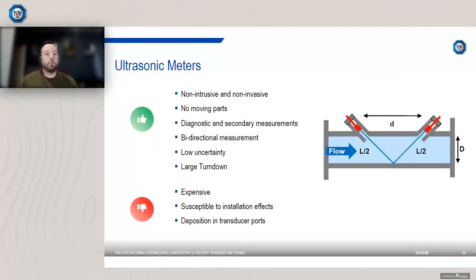So why are ultrasonic meters popular for custody transfer applications? Well, they're non-intrusive and non-invasive, so they're not typically going to introduce a pressure drop in the pipeline, and you can even get clamp-on ultrasonic meters that clamp onto the outside of the pipe. Now, these typically won't have the uncertainty you're looking for in custody transfer, but they're very good diagnostic tools. So if you have a system where you can't break the line and install a flow meter, you can use a clamp-on ultrasonic meter for those cases.